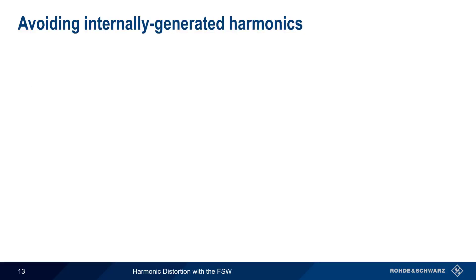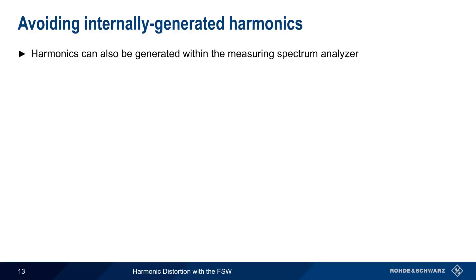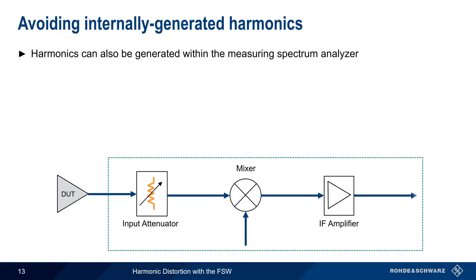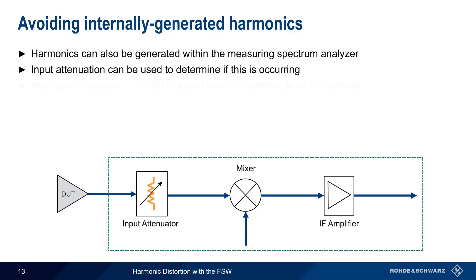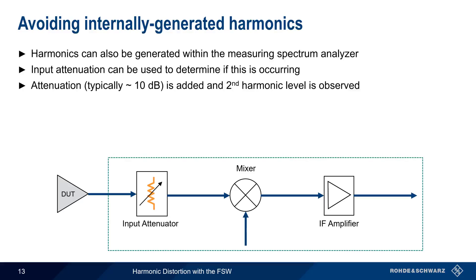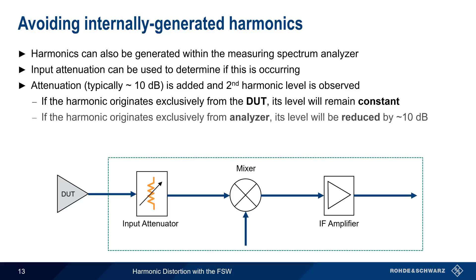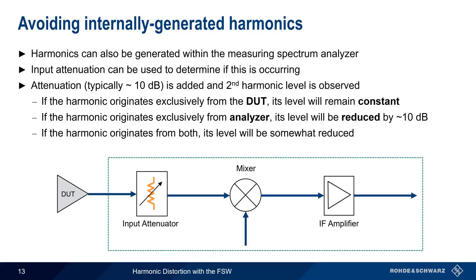One potential source of measurement inaccuracy comes from the fact that harmonics can sometimes be generated within the spectrum analyzer itself. When the DUT's signal enters the spectrum analyzer, it first passes through a passive input attenuator, but then passes through numerous active devices such as mixers and amplifiers, which can create harmonic distortion. An easy way to check if this is happening is to use input attenuation. Normally, about 10 dB of attenuation is added and the measured second harmonic level is observed. If the harmonic is exclusively from the DUT, its level will remain constant. If it originates exclusively from within the analyzer's active components, attenuating the input by 10 dB will reduce the measured harmonic level by approximately 10 dB. If the harmonic originates from both, its level will be somewhat reduced by adding input attenuation.